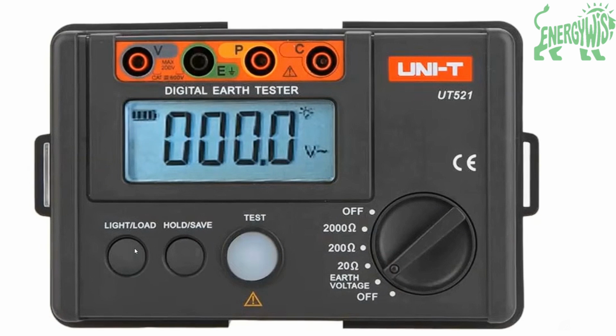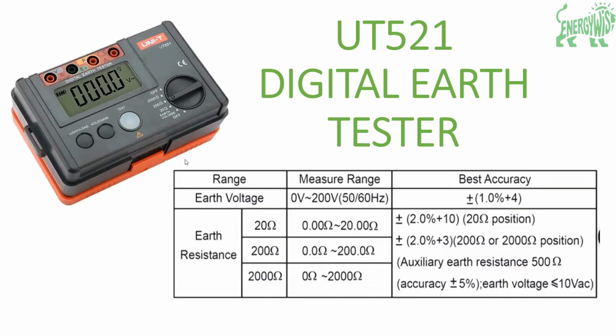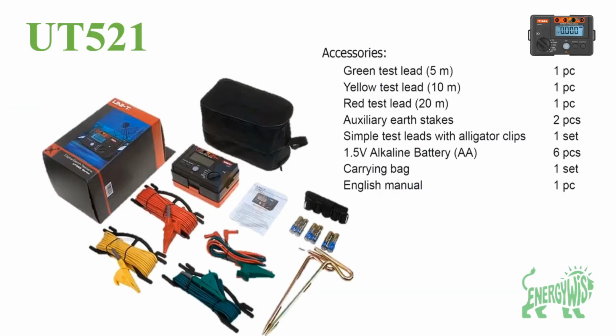the earth voltage. And here we can see the load, hold, and save functions. We can hold and save a reading, and when we want to start testing, we press this button. Here is the range: for example, if we measure with the 20 ohm range, we can measure from 0 to 20, but the accuracy level for this range will be 2%, and it goes the same for the others. And the earth voltage should be less than 10 volts, so we can see it that way.